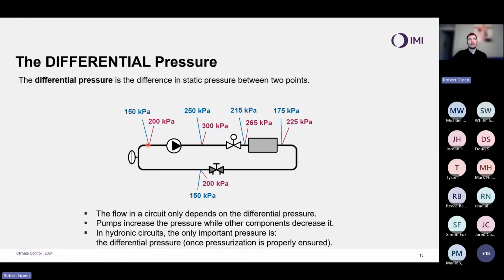And again, let's look at this same example with a different starting point, starting at 200 kilopascals. Once again, my pump increases the static pressure, going from 200 to 300 kilopascals. It's that same 100 kilopascal difference. My control valve, again, takes out 35 kilopascals, 300 to 265. My terminal unit takes out 40, 265 to 225. And finally, the balancing valve is taking out that 25 kilopascals, that extra piece to bring me back to 200 kilopascals once more. And it is this difference in pressure that is driving flow through the system.